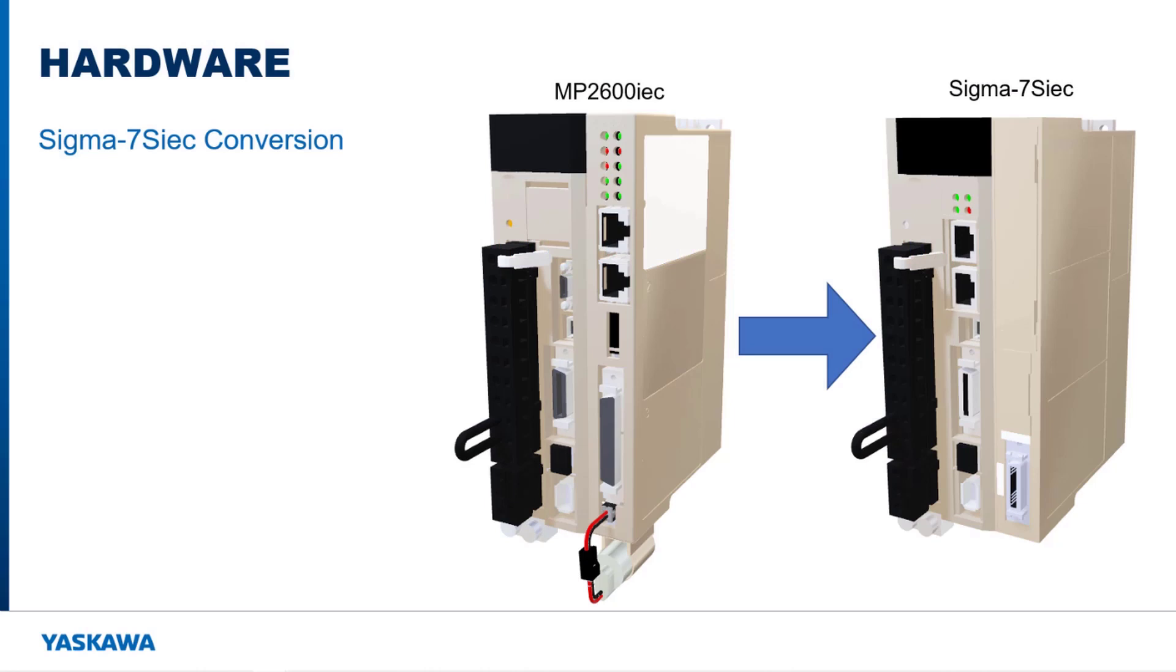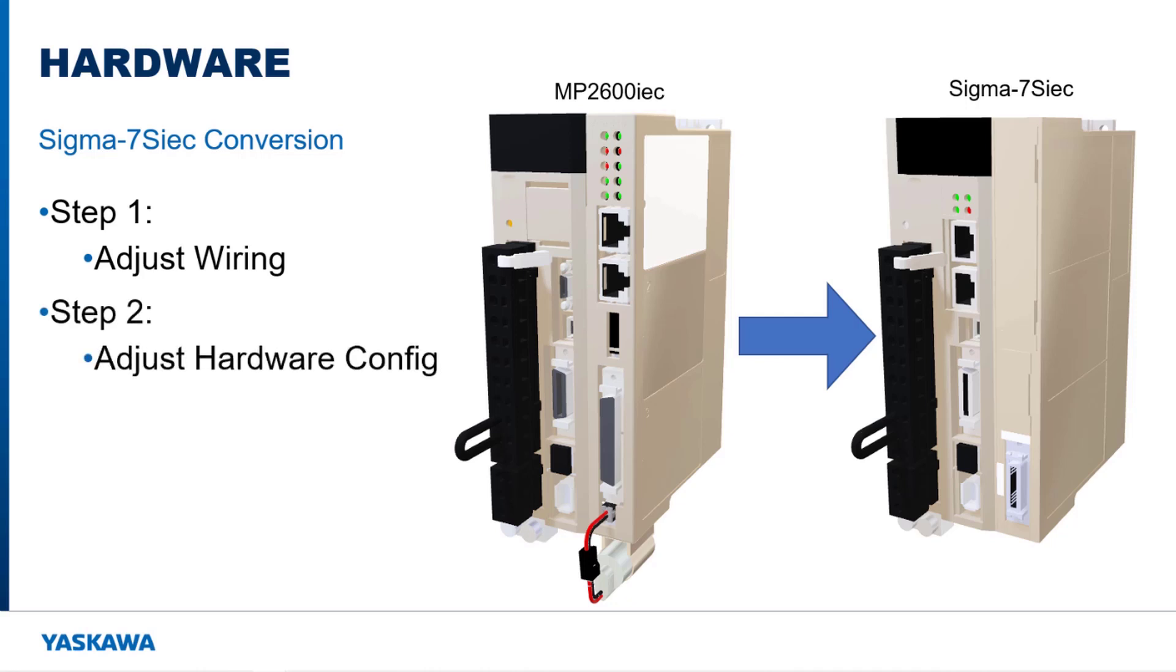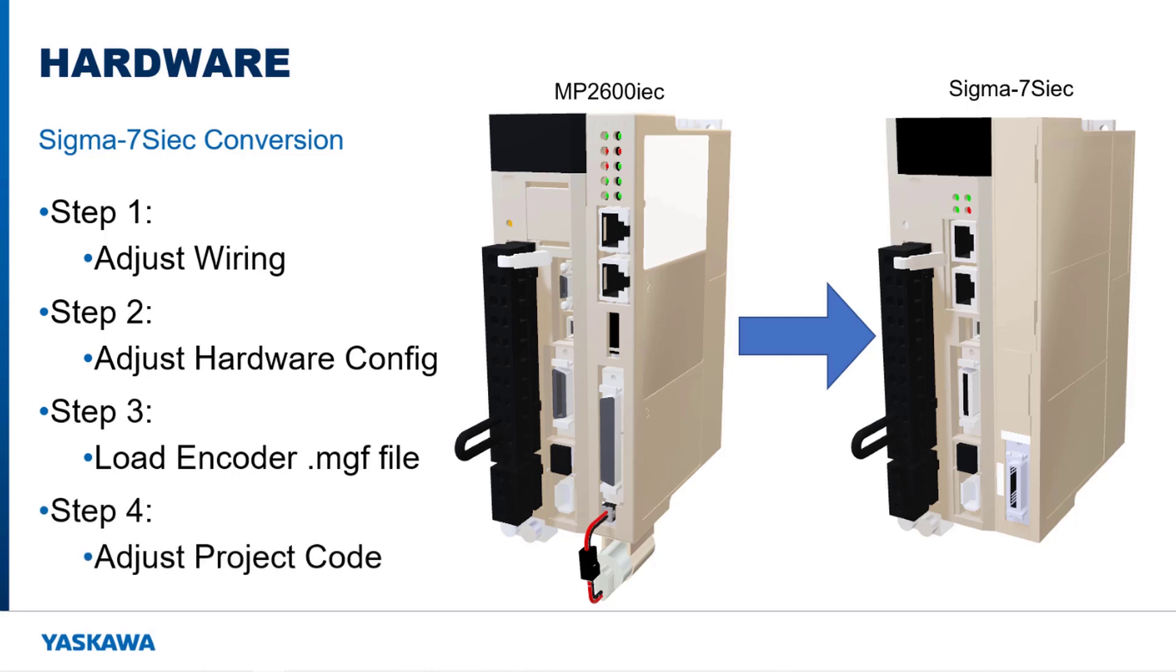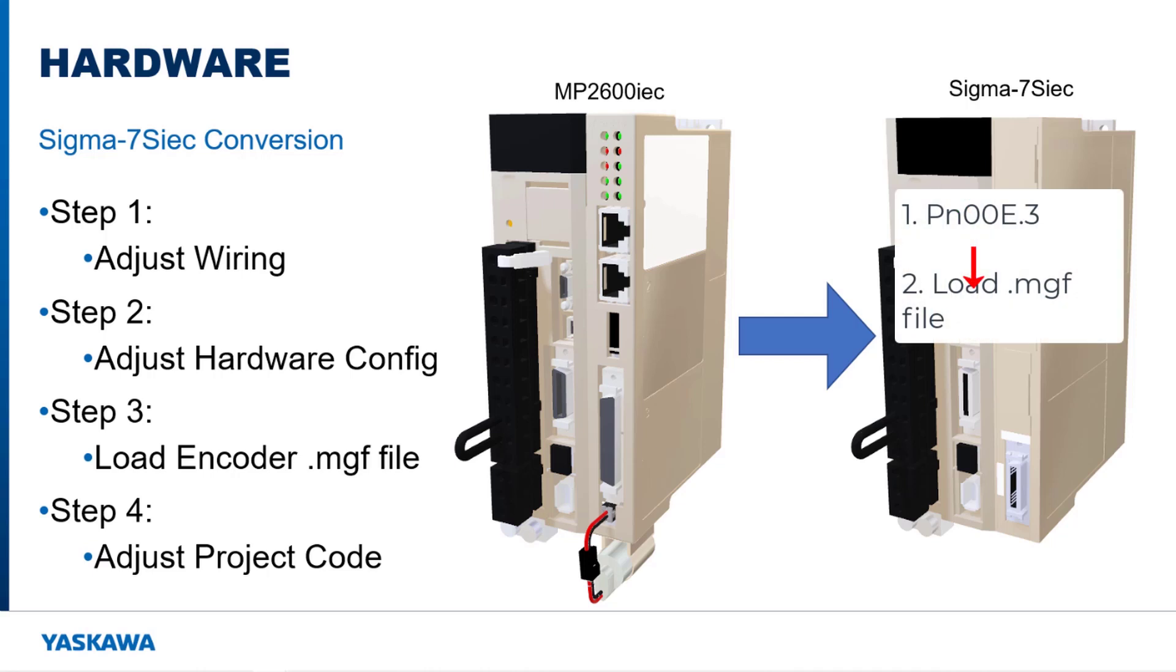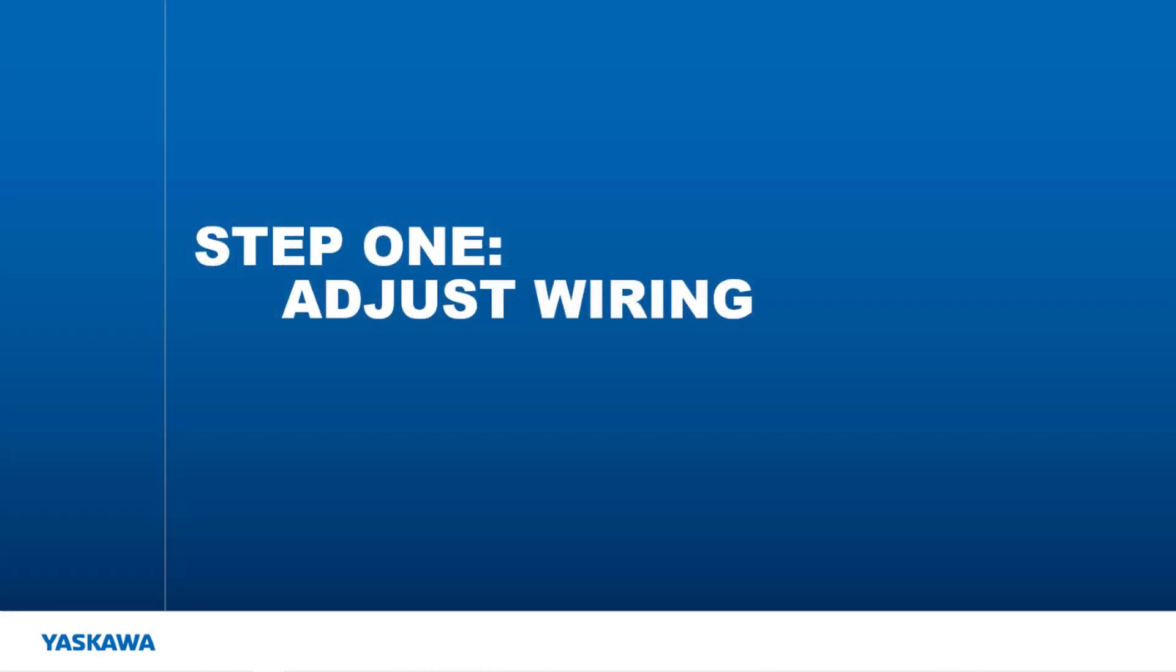There are four major steps that need to be done to complete this conversion. Step 1 is to adjust the wiring to the controllers. Step 2 is to modify the hardware configuration. Step 3 is to load the encoder manufacturing file into the feedback option card. Step 4 is to adjust the project code. These steps can be done in any order as long as PN00E.3 is set in hardware configuration before the encoder manufacturing file is loaded.